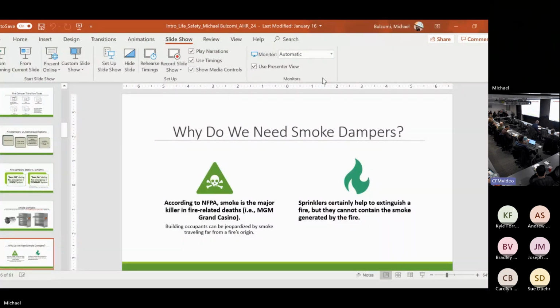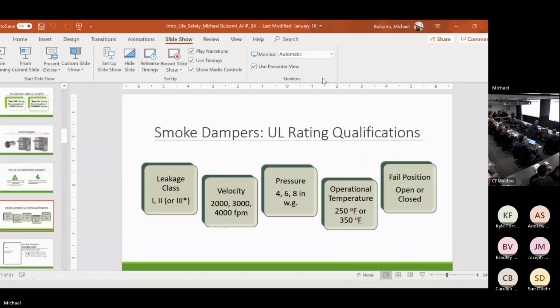Why do we need smoke dampers? I already told you, smoke is the major killer. Fire destroys, but smoke kills. Smoke travels very far, very fast from the point of origin. So we need those smoke dampers to isolate and trap that smoke.